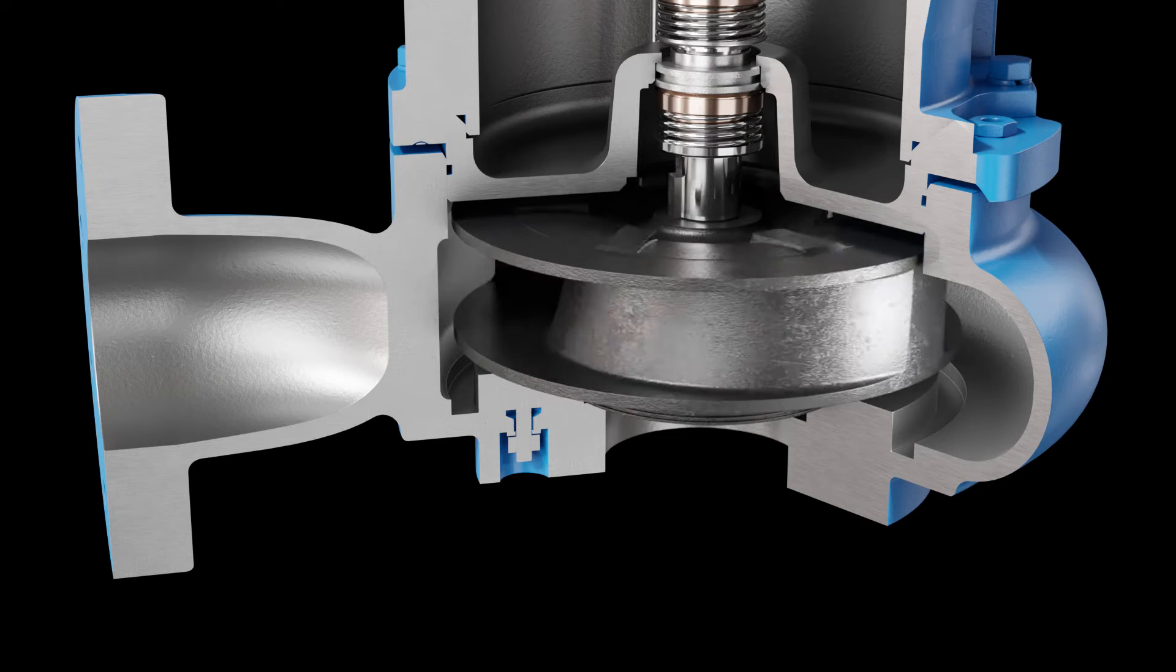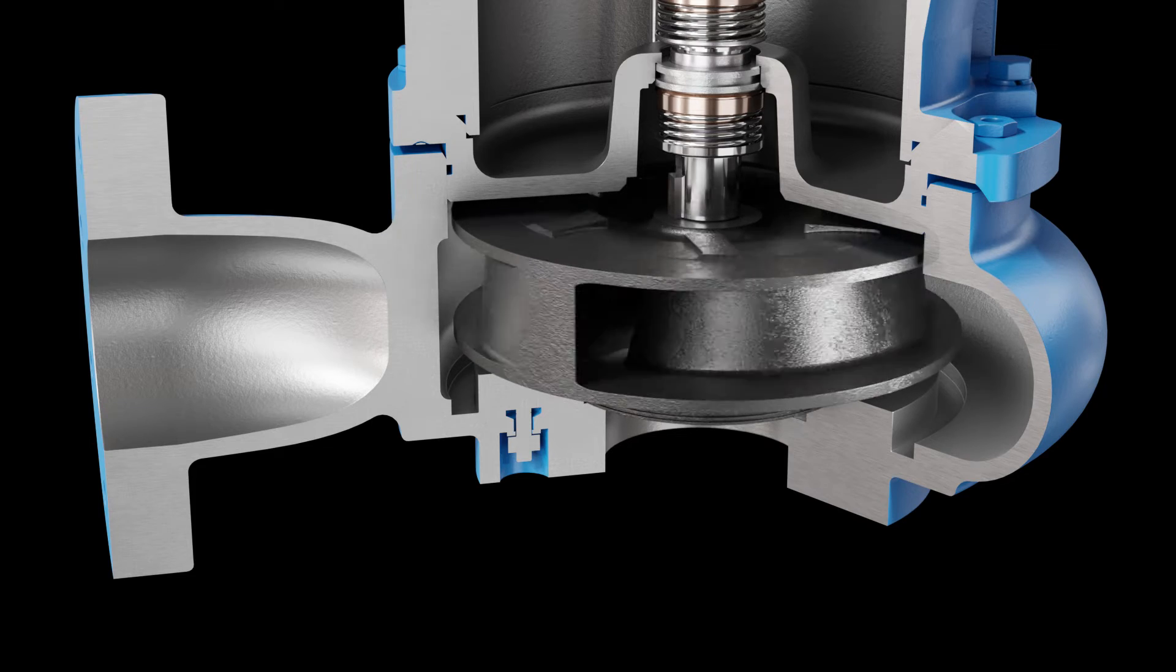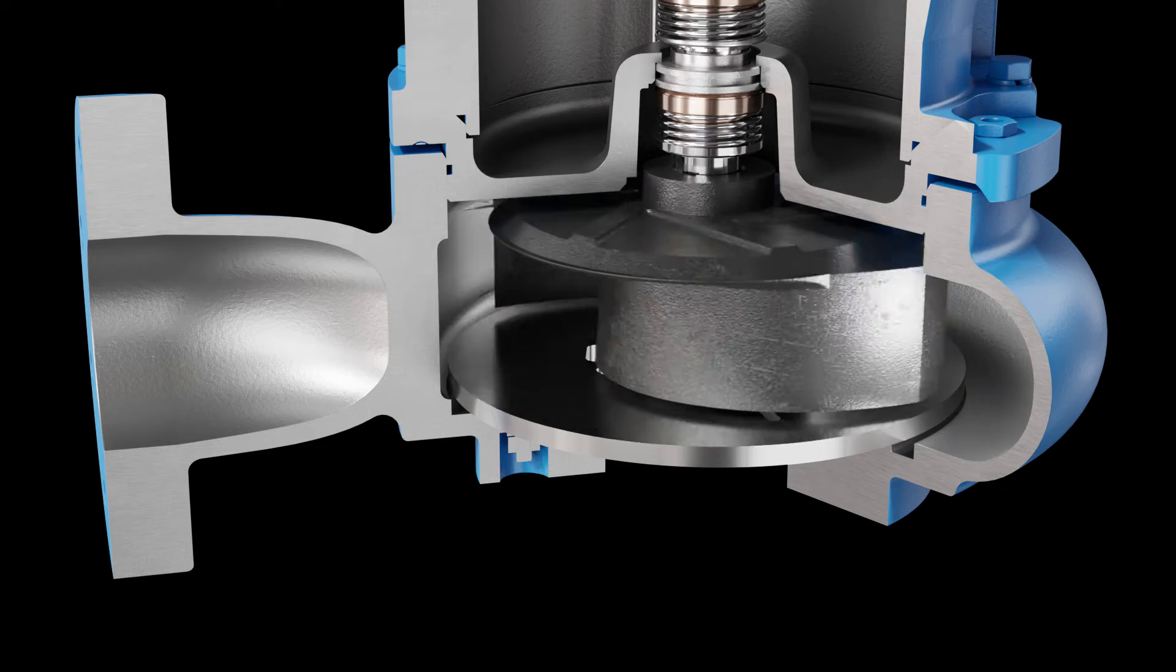Channel model options include standard enclosed, semi-open, or continuous vane Eradicator Plus impellers. Enclosed models provide 3-inch solids passage capabilities while offering optimal efficiencies. Semi-open models are equipped with a self-cleaning wear plate and rear pump-out vanes to help prevent the buildup of debris.